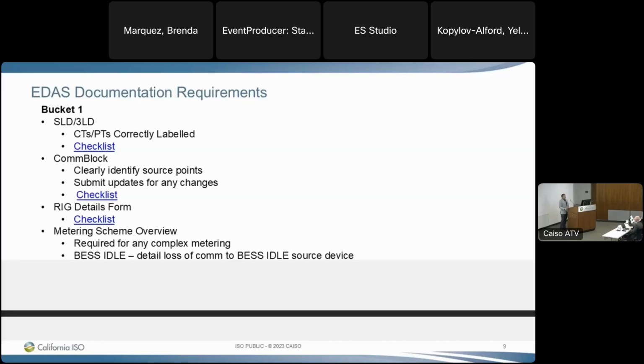For the com block, it's really important to identify those source points from where they are sourced at the site. During the point-to-point test, we often see that during pre-testing there were changes made to where the source devices or points for those devices are coming from. We really want those changes communicated early so we have that visibility for the point-to-point test, so we're not facing surprises during the point-to-point or having to submit that com block after the point-to-point.